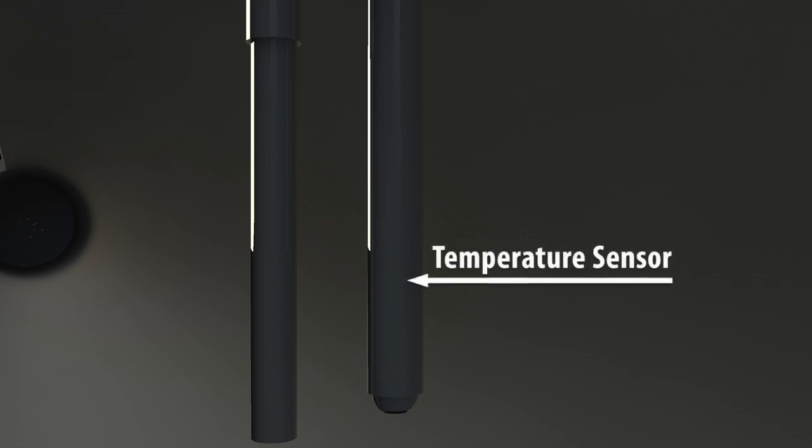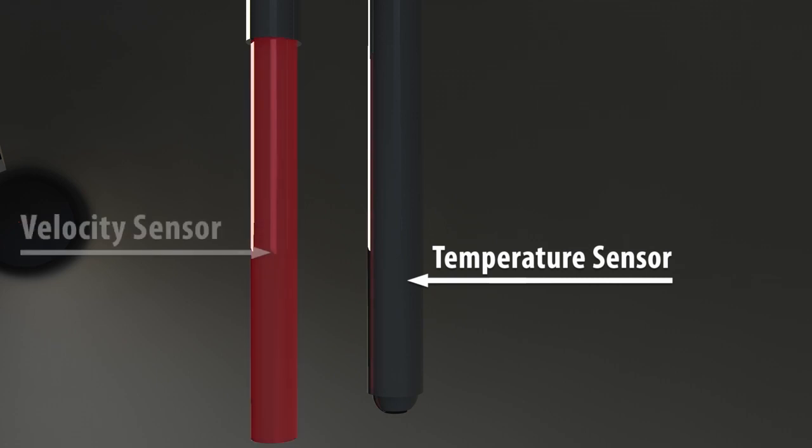Thermal flow meters have two sensors immersed into the flow stream. One is a temperature sensor, which measures the actual gas temperature inside the pipe as a reference, regardless of the flow velocity. The other is a heated sensor, called the velocity sensor, illustrated here in red.